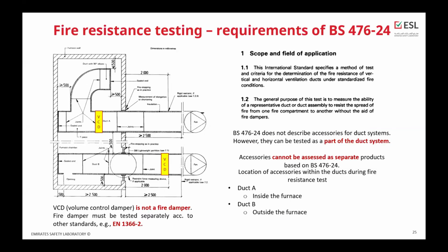BS 476 part 24 is referring only to the duct assembly. It's not describing the accessories of the duct system. However, we can do the test of these accessories, but as a part of the assembly, as a part of the duct system. The accessories cannot be assessed separately from the duct. So where shall these accessories be located? In terms of duct A, we have these accessories inside the furnace. For duct B, those accessories shall be located outside the furnace to assess all criteria.